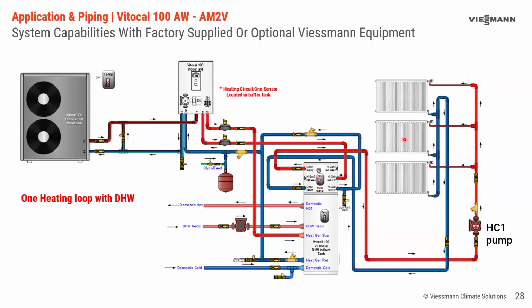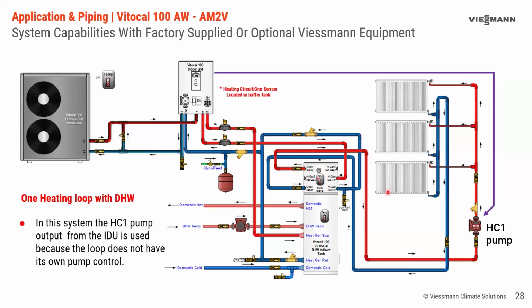But in a lot of cases, you might have motorized zone valves with thermostats. And it doesn't matter which way you do that, because we're not going to take anything from here, any brain from here that says I need heat, and feed it back to the indoor unit. We're going to let the indoor unit keep the buffer tank hot, and the building is separated from that. The only connection we have in this case is we have the heating, cooling circulator pump running on circuit 1. So where the air handler had its internal pump, we didn't use that circuit. In this one here, we are using that circuit.